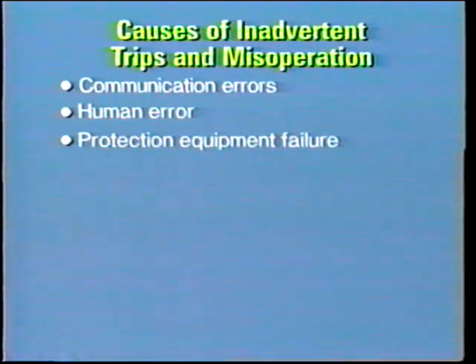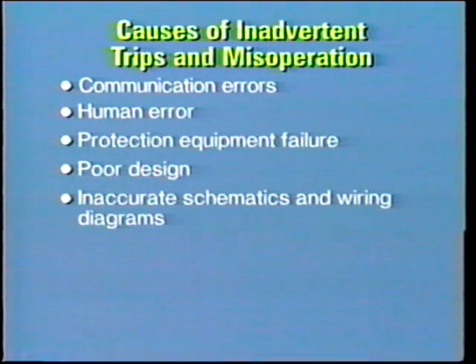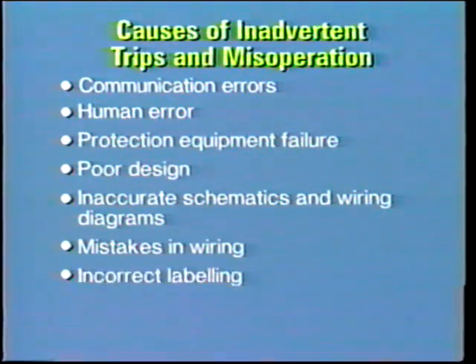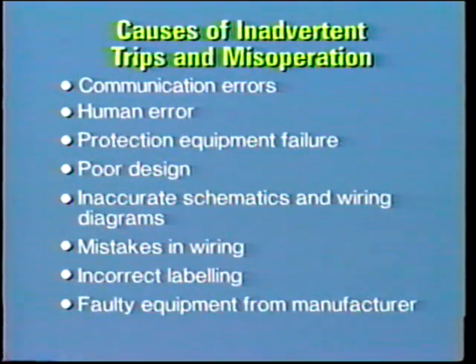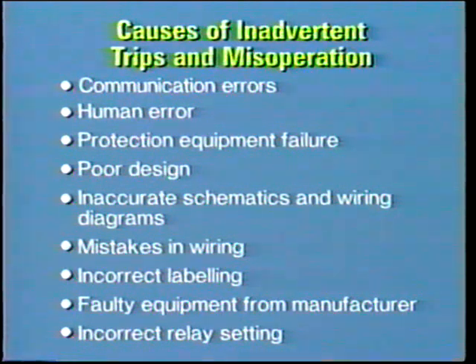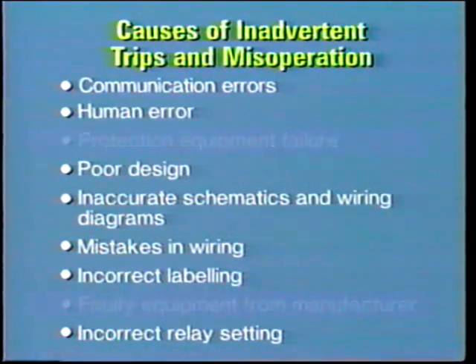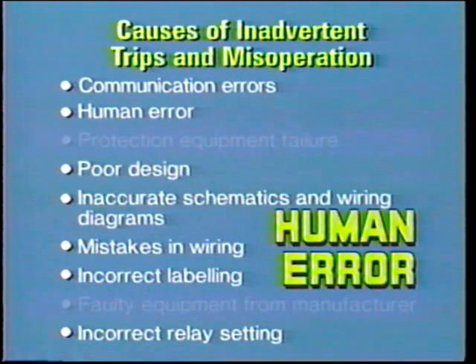There are several main causes of inadvertent trips and misoperation that immediately come to mind. Communication errors, people getting different meanings from the same message. Human error, as indicated in our first example. Protection equipment failure under actual operating conditions, our second example. Poor design, inaccurate schematics and wiring diagrams, mistakes in wiring, incorrect labeling and identification of equipment, faulty equipment from the manufacturer, incorrect relay setting. Note that most of these items are a result of human error somewhere in the chain.